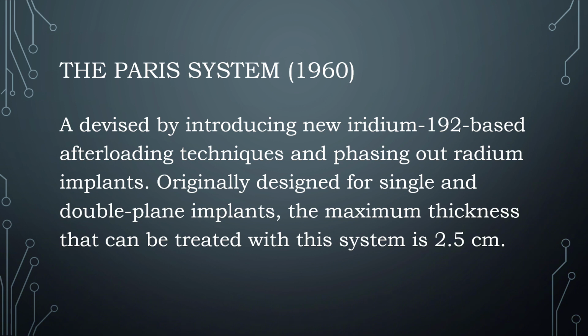The Paris system was devised by introducing new iridium-192 based afterloading techniques and phasing out radium implants. Developed in the 1960s, it requires the target's thickness, length, and width, with spacing dictated by the implant's thickness, and the number of sources by the cross-sectional area. The prescription dose is 85% of the basal dose, calculated by averaging the minimum dose between adjacent equidistant sources in the transverse plane. Originally designed for single and double plane implants, the maximum thickness that can be treated with this system is 2.5 cm.